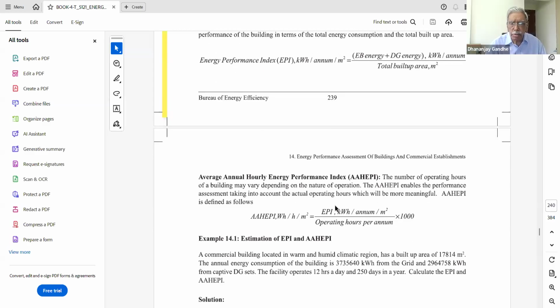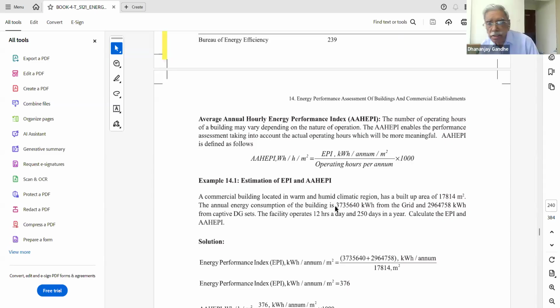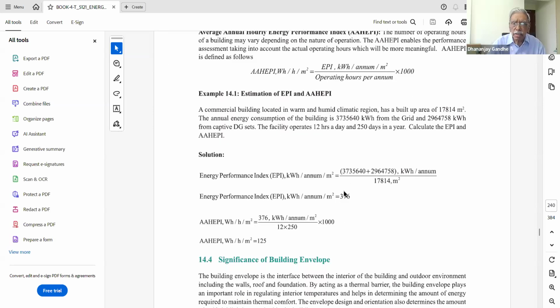Then the second parameter, which is also used for comparison of energy efficiency of a building, is the average annual hourly energy performance index. The short form is AAHEPI. This is defined as the energy performance index divided by the number of operating hours in a year. So EPI is expressed in kilowatt hours per square meter per year, and operating hours per annum. These two figures need to be worked out, and there is an example solved here to explain how to calculate this.